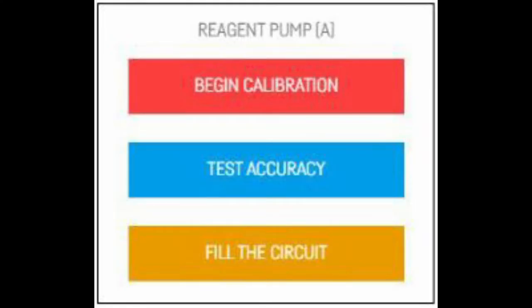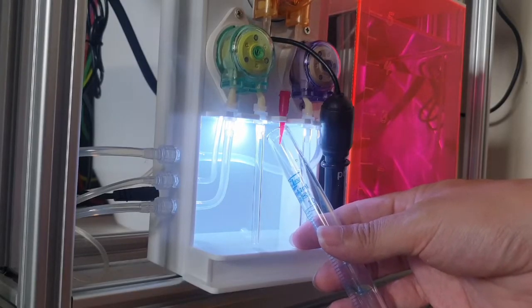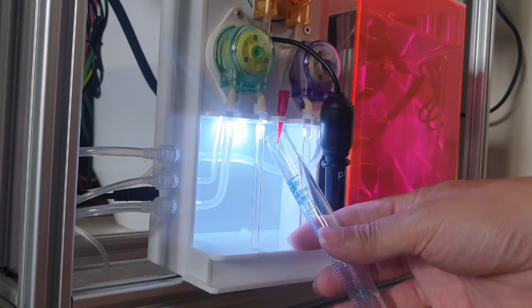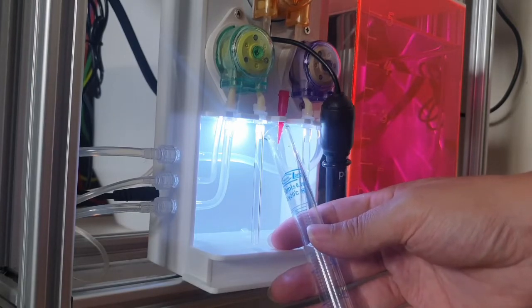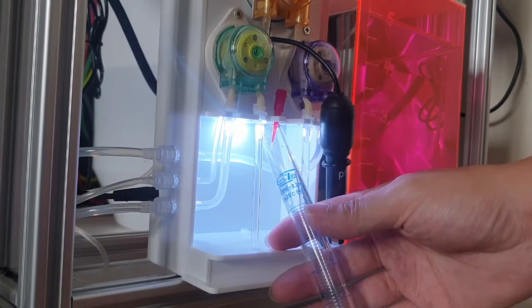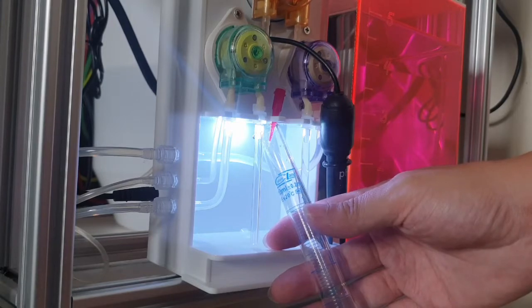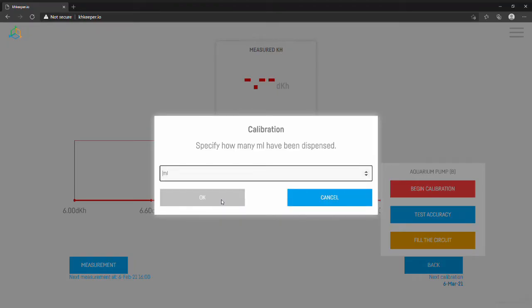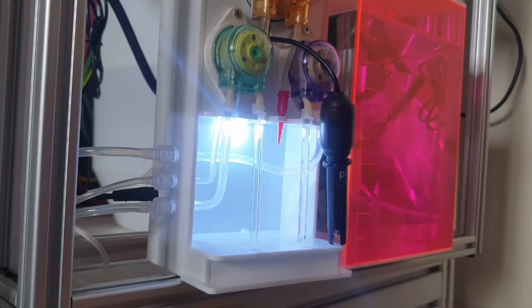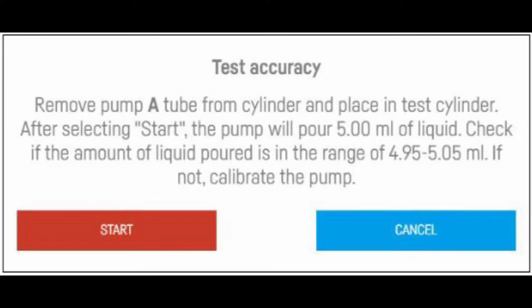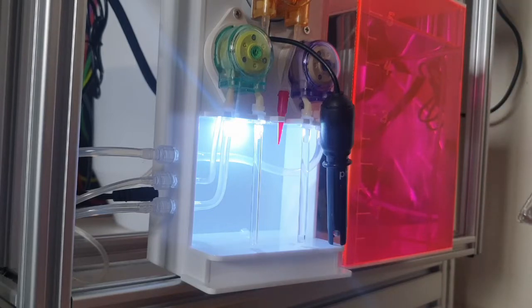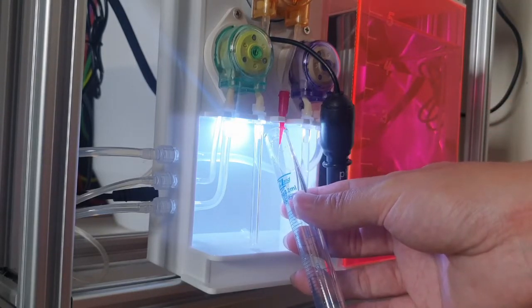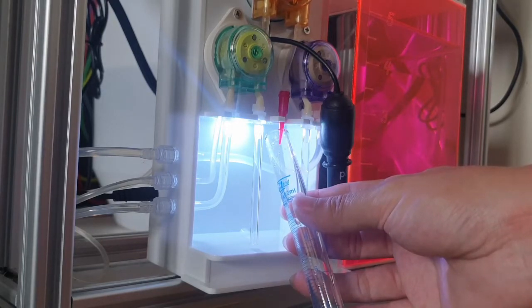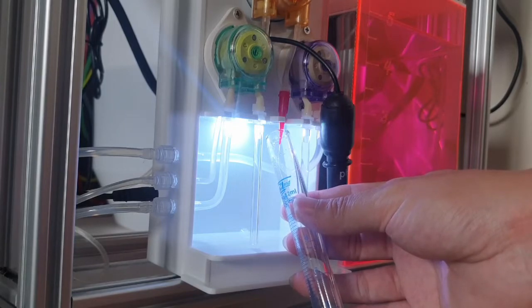Next, I will start calibrating the reagent pump. Similar steps to the above. The only difference is that the water volume, or the reagent volume, is a lot lower, so I'm using the 10 ml flask over here. Once again, we have to do a test to ensure everything is calibrated properly.